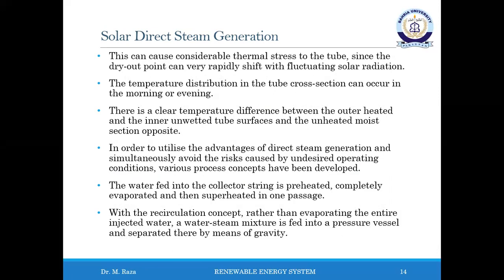A feature of the once-through process is its simple structure. The water fed into the collector string is preheated, completely evaporated, and then superheated in one passage. With the recirculation concept, rather than evaporating the entire injected water, a water steam mixture is fed into a pressure vessel and separated there by means of gravity.